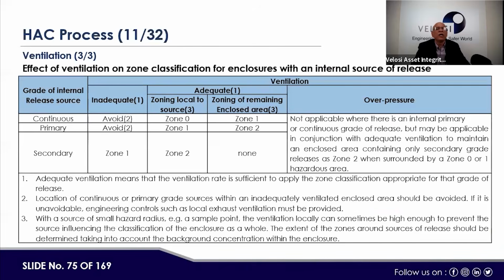Now here, the same thing is discussed: the effect of ventilation on zone classification for an enclosure with an internal source of release. Grade of internal release source, continuous, primary, secondary, then accordingly inadequate or adequate ventilation. It should be zone 0, zone 1, zone 2, and then zoning of the remaining enclosed areas: zone 1, zone 2, and none.